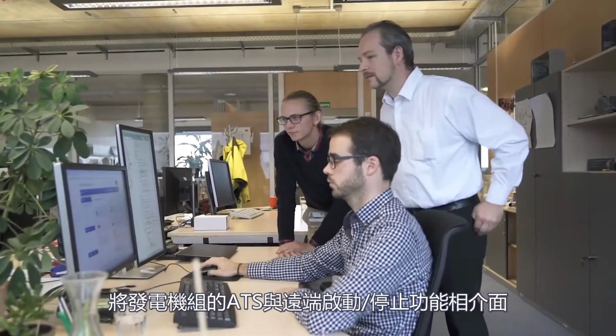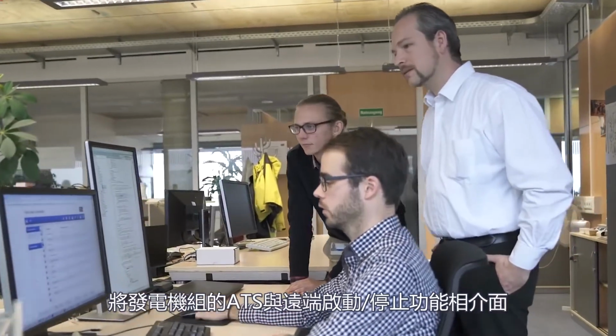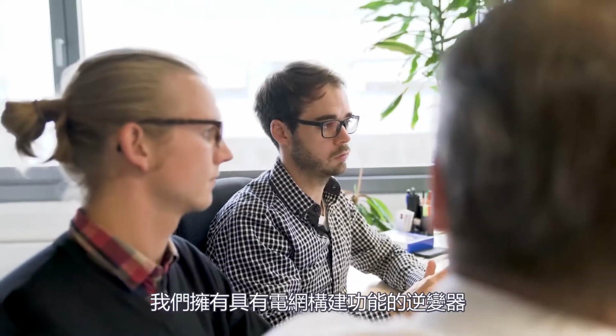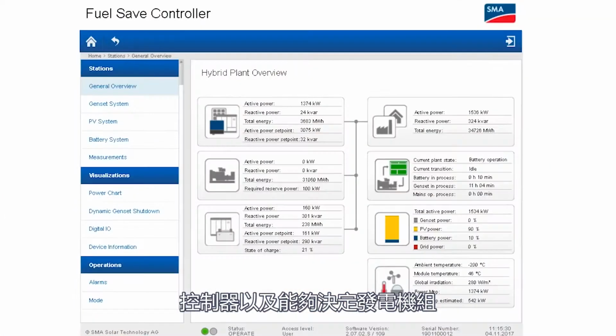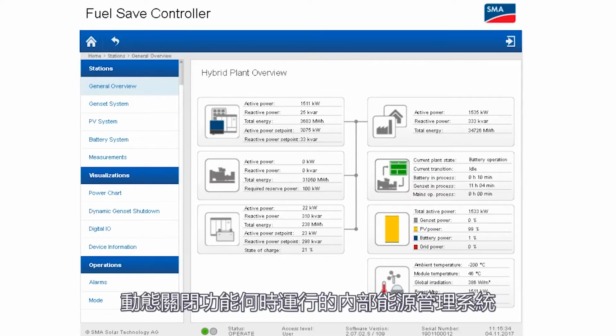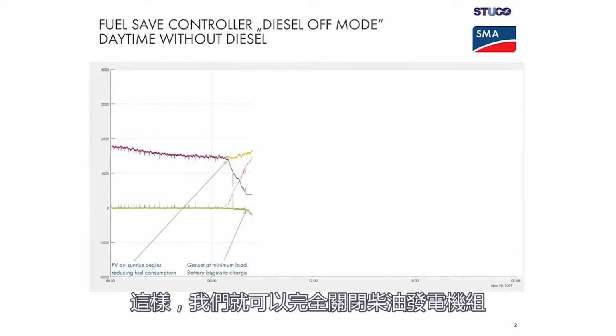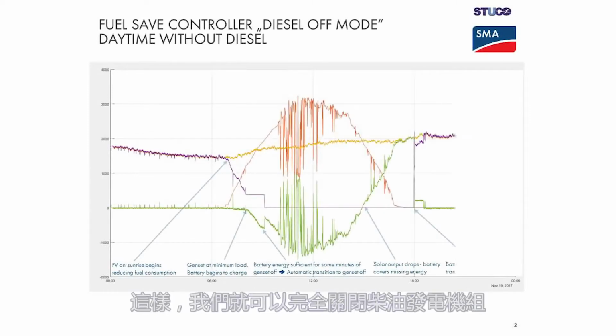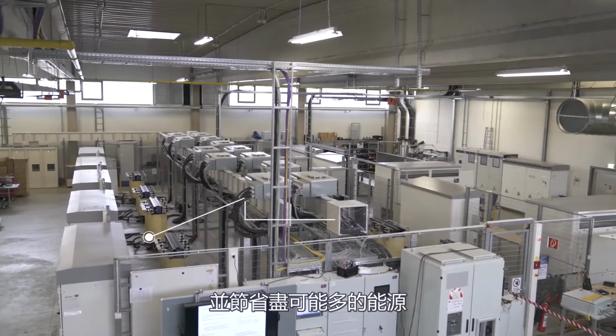We're interfacing 8 diesel gensets with remote start-stop functionality. We have grid-forming inverters, an overlaid plant controller that controls the whole environment with frequency and voltage control, and an internal energy management system that decides when the dynamic genset shutdown should be run or not, so we can completely shut down the diesel gensets and save as much energy as possible.